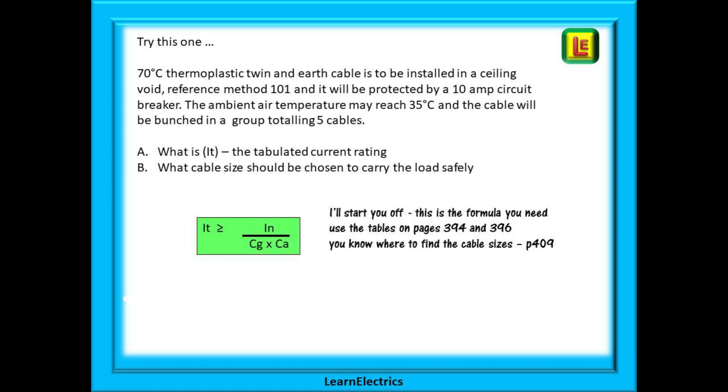Now try this one. 70 degree thermoplastic twin and earth cable is to be installed in a ceiling void using reference method 101. And it will be protected by a 10 amp circuit breaker. The ambient air temperature may reach 35 degrees centigrade. And the cable will be bunched in a group totalling 5 cables. What is IT? The tabulated current rating. And what cable size should be chosen to carry the load safely. This is the formula that you need. Use the tables on page 394 and 396. Once you have a current size you know where to find the cable sizes on page 409. Pause the video whilst you work it out.